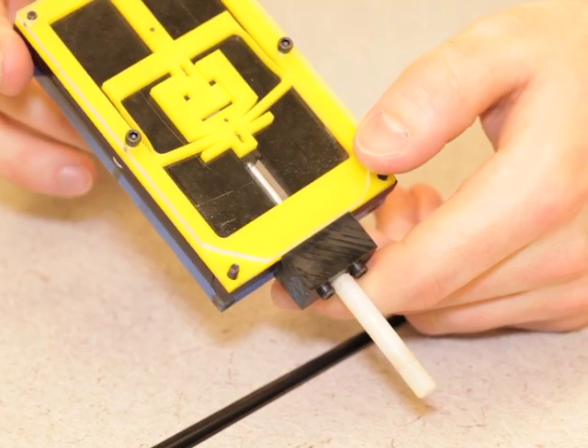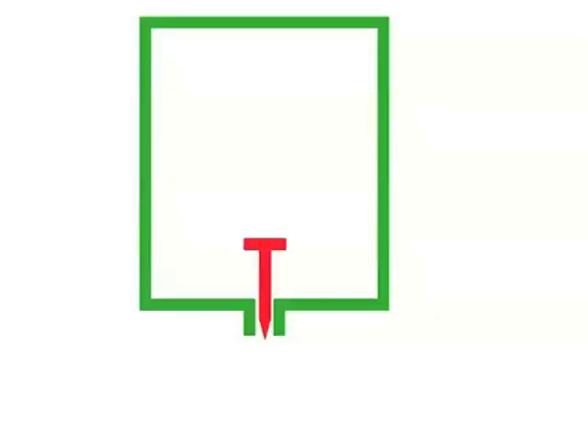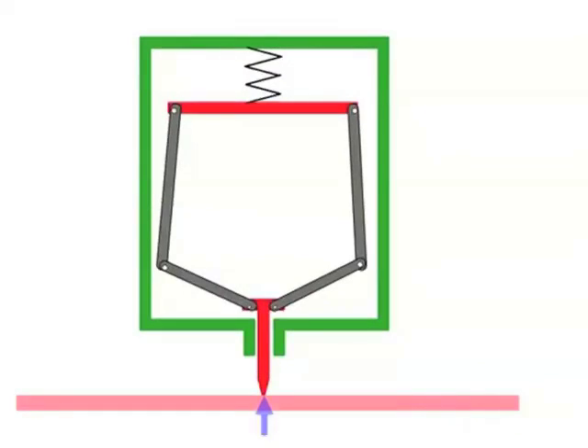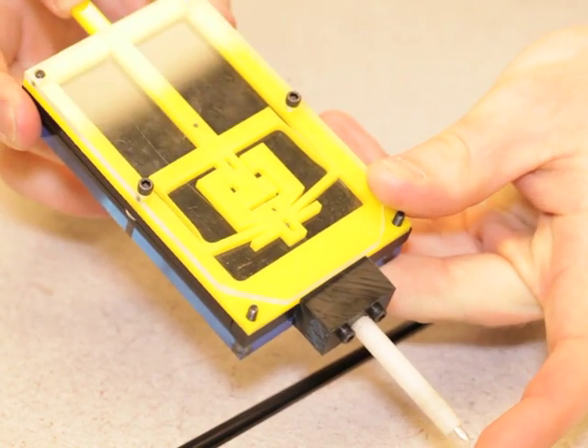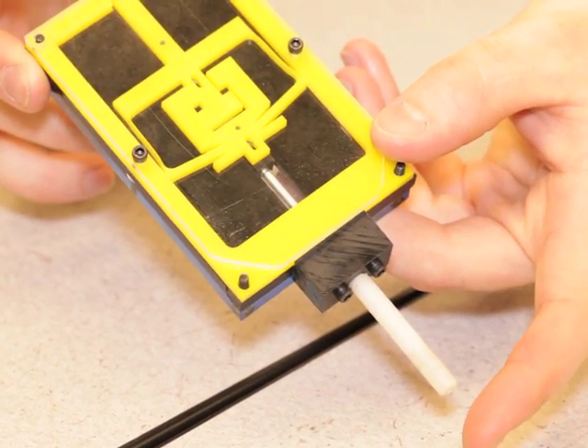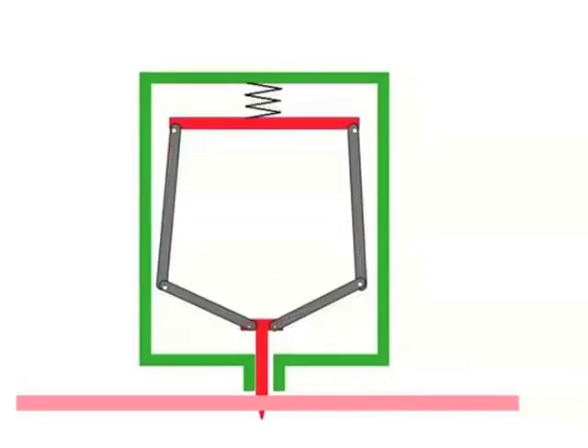The device is essentially a standard puncture device, but it has within it a mechanism that includes a retraction spring and a flexural linkage. As long as the sharp cutting tip is pressed against tissue and cutting through it, the mechanism is locked against the walls with friction, which opposes the retraction spring and keeps the tip exposed and cutting. As soon as the tip punctures tissue, the force on it goes to zero, the mechanism unlocks, and it retracts the tip — opposing that forward acceleration.